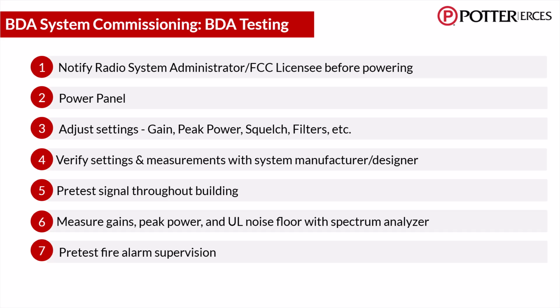When your testing has been conducted and everything looks to be working properly and your isolation test suggests there is no potential interference or feedback expected to be created, there can still be unforeseen noise created once the BDA is connected to the donor antenna. For lack of a better term, we call this the ghost in the machine. It's important that you notify the FCC licensee before you connect the ERCES to the radio network so that if there is any adverse effect on the radio network's integrity, the system can be powered down quickly and reduce the impact to first responders relying on that radio tower's functionality.